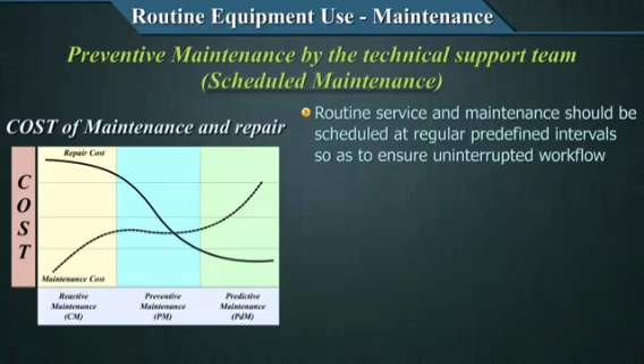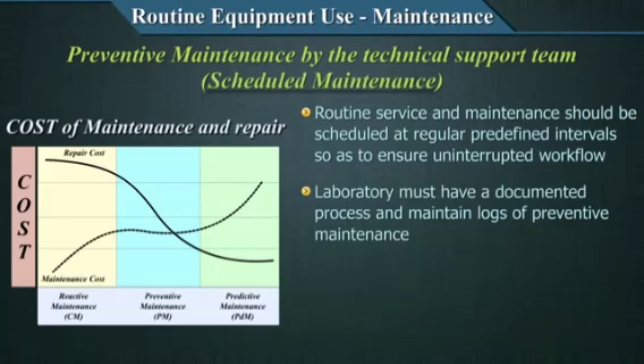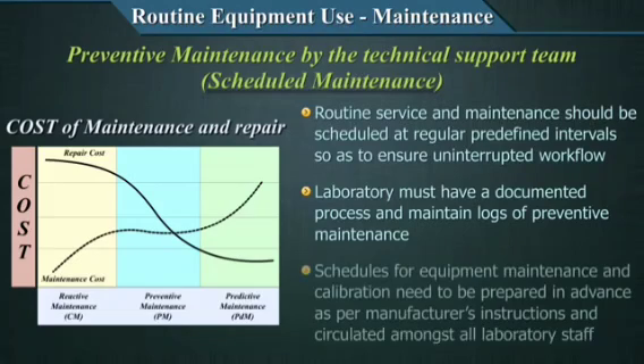This is assuming that you have a valid contract with your equipment manufacturer or a third party. The laboratory must have a documented process and maintain logs for preventive maintenance. Very important again, documentation. The schedule for equipment maintenance and calibration needs to be prepared in advance as per the manufacturer's instructions and circulated among all laboratory staff so that it can be rigorously adhered to.